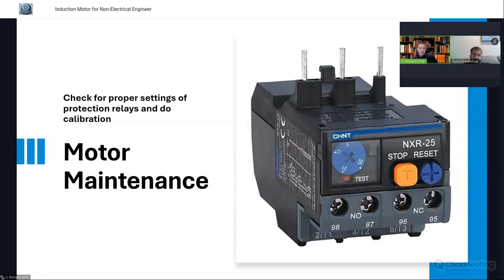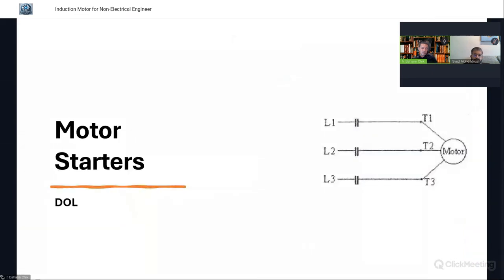And also some of the settings are made during the engineering stage, and then this needs to be checked for proper setting, because sometimes people, we do not know, change the setting without asking whether it can be changed or not. So this needs to be checked regularly as well.